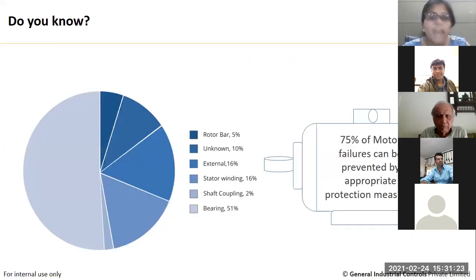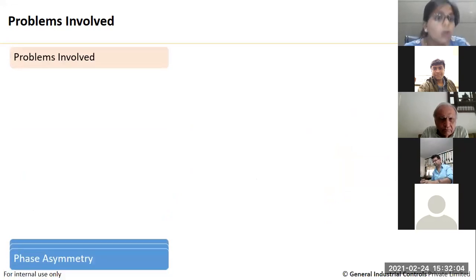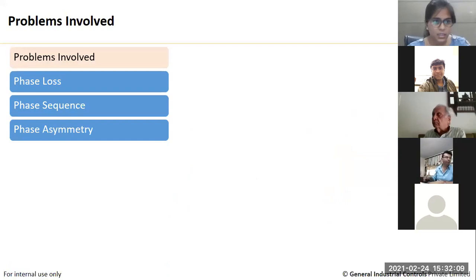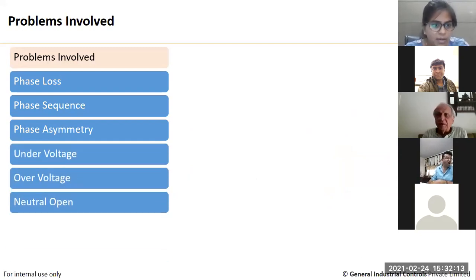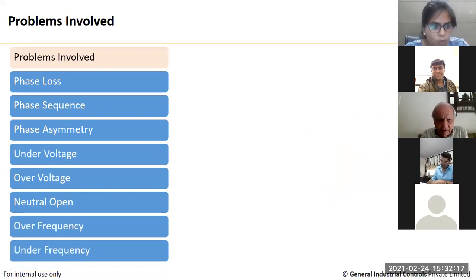So why do we monitor? Let's take a common example: motor failure. There are 75% of motor failures which can be prevented through a few protection measures. There are three critical parameters: current, voltage, and frequency. Because of various combinations of these, systems or motors usually get hampered. The common issues include phase loss, phase sequence, phase asymmetry, under and over voltage, and over and under frequency. These are common problems we encounter in day-to-day life.